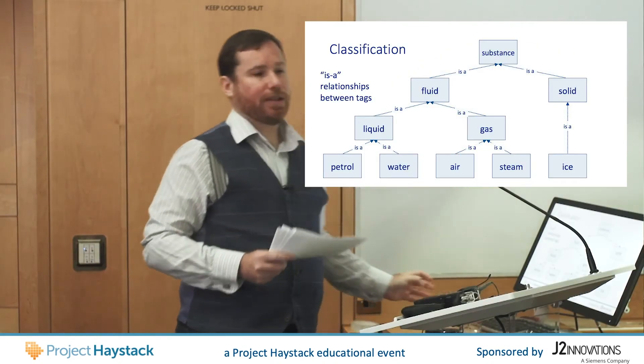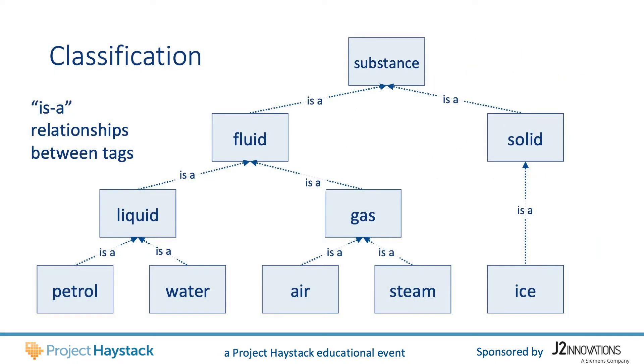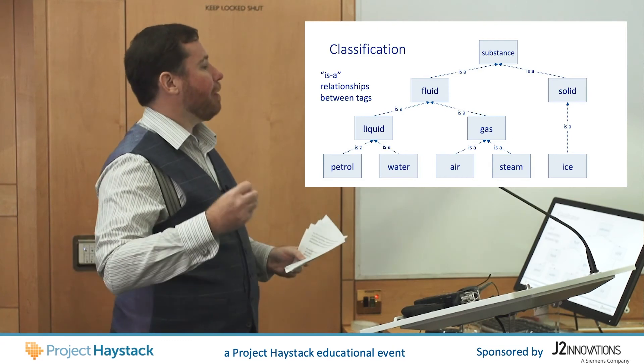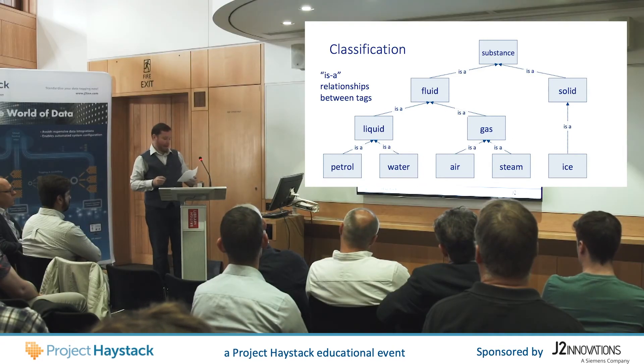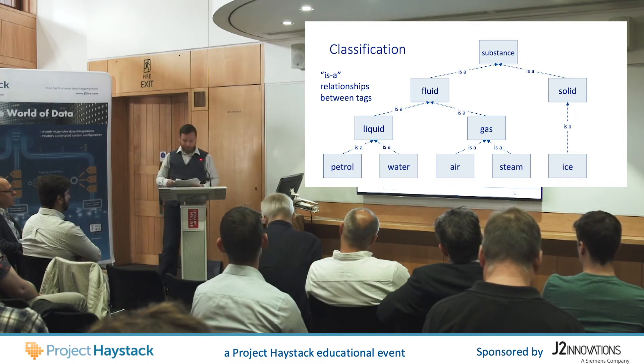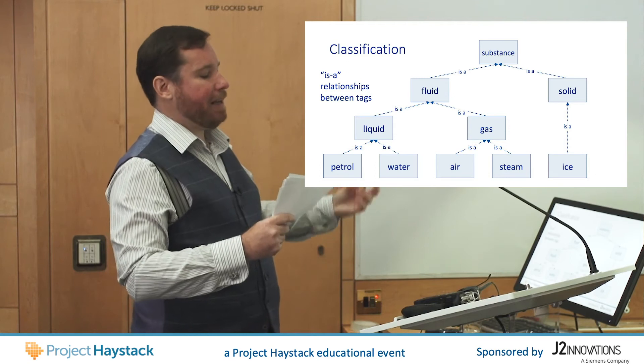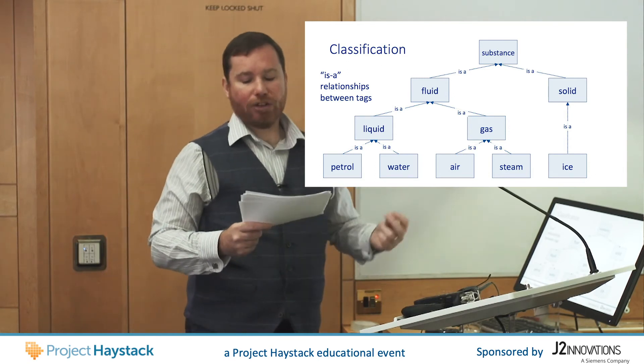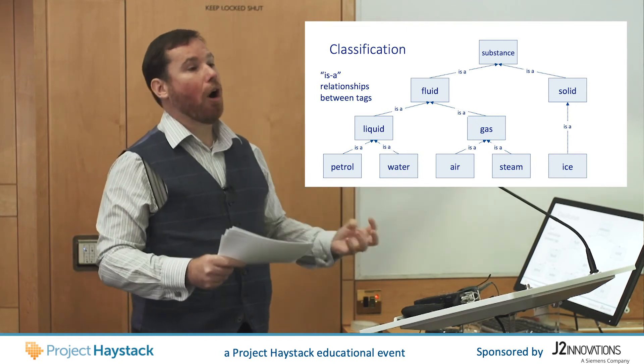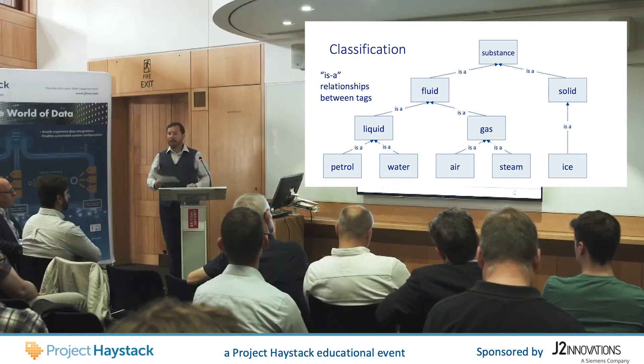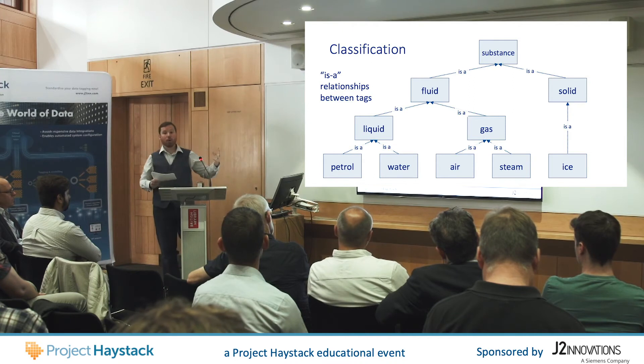The next thing Project Haystack 4 introduces is a means of classification. In a way, this is where tags are used to describe tags. When we look up a definition of a tag like water, it points to another tag and says, hey, I'm one of these. So water is a liquid, is a fluid, is a substance, and so on. It lets us build up a hierarchy that describes what tags are. This means that I only need to tag my data with water, and then I can automatically infer all the other tags from that. Project Haystack 4 gives a mechanism to describe hierarchies and also provides pre-made libraries of common building automation tags and their hierarchies, so I have a concrete language that already describes things like water, ice, and air.